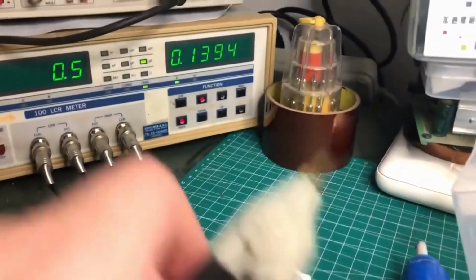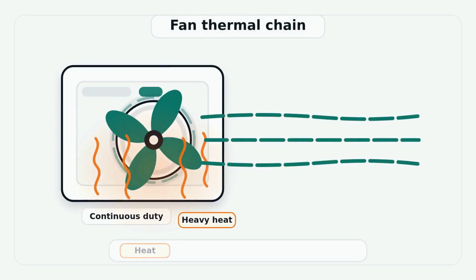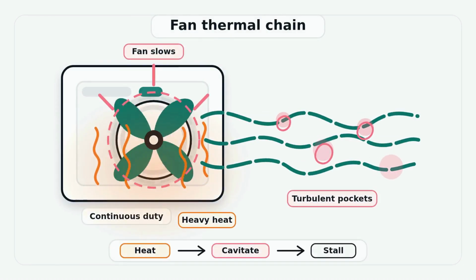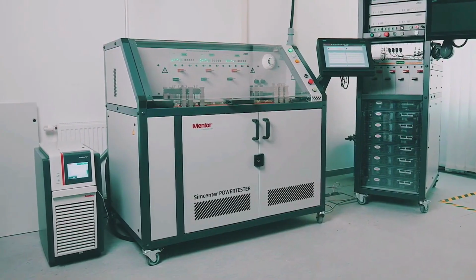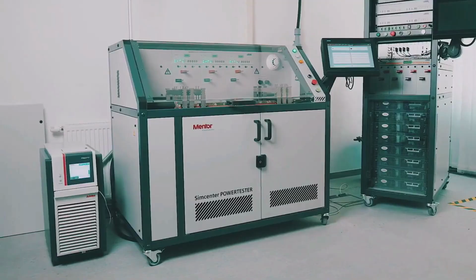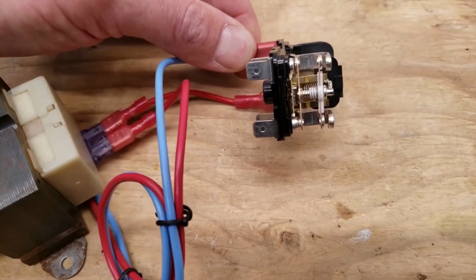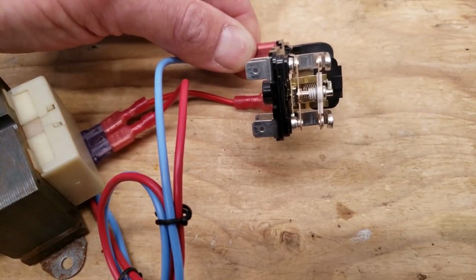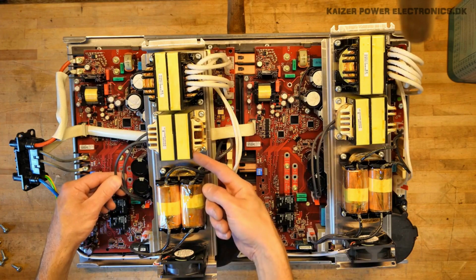Capacitors drift out of tolerance. Fans undersized for continuous duty cavitate and stall. Power semiconductors cycle through temperature swings that fatigue solder joints. Relays stick. The damage is cumulative and invisible until output is already gone. So the criteria are specific.